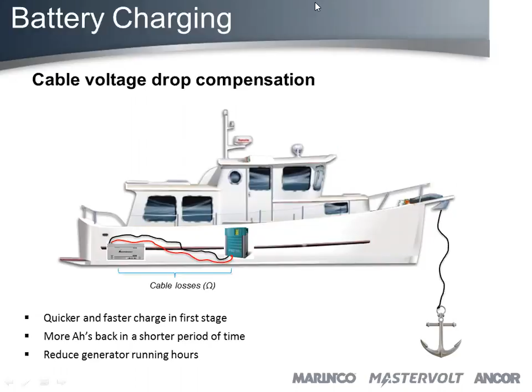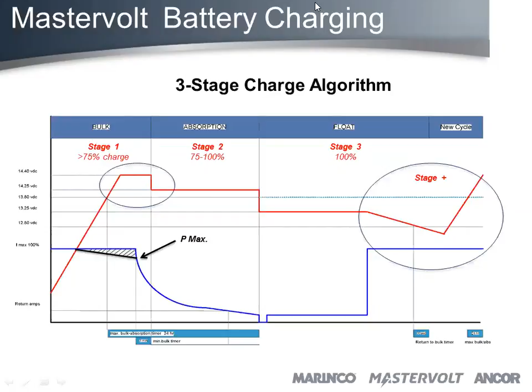And it's only 0.15 volts. So we took an average installation where the battery charger is about 6 to 8 feet away from the battery bank. That voltage drop is at that maximum point about 0.15 volts. So we're pushing that extra voltage in. The battery will only see 14.25. The cable losses will basically eat that 0.2 or 0.15 volts, and that will give you some extra amp hours back into the battery bank.